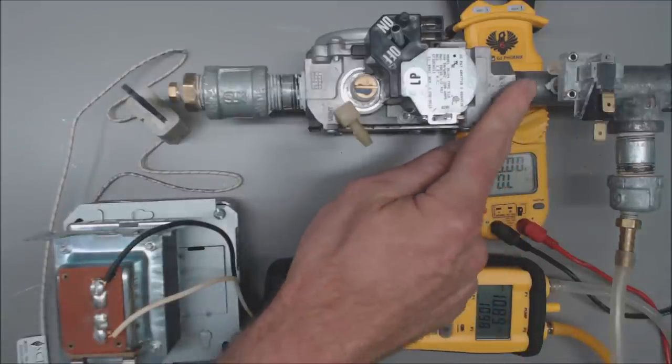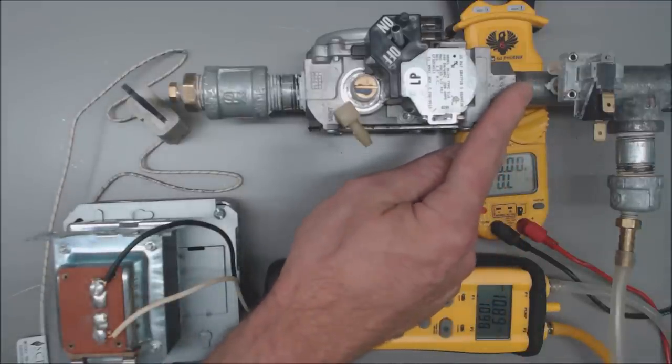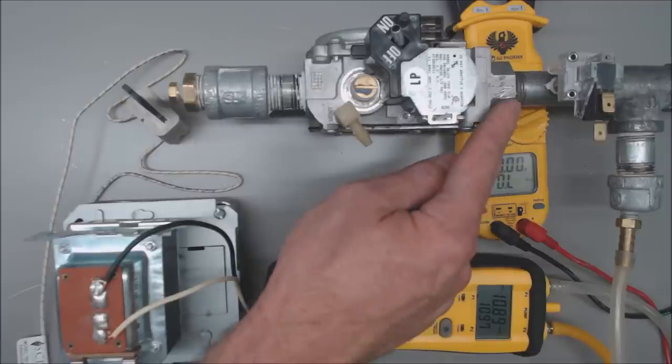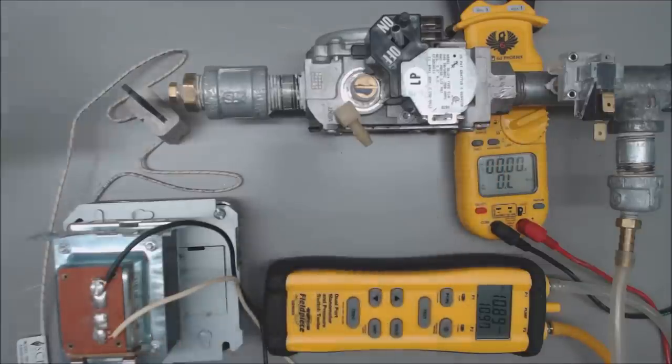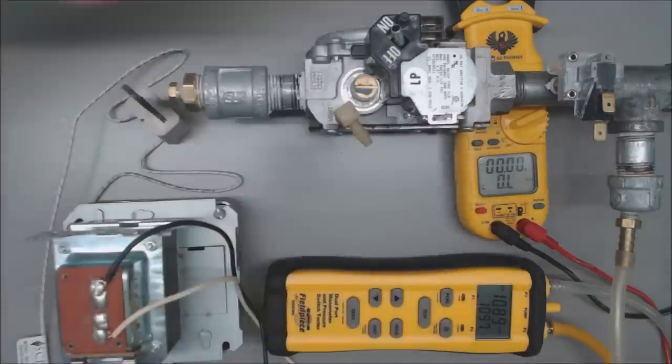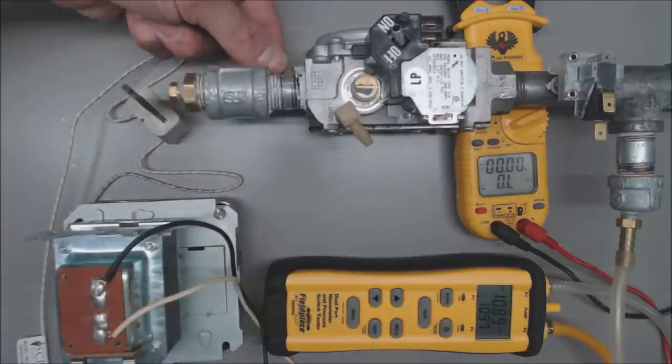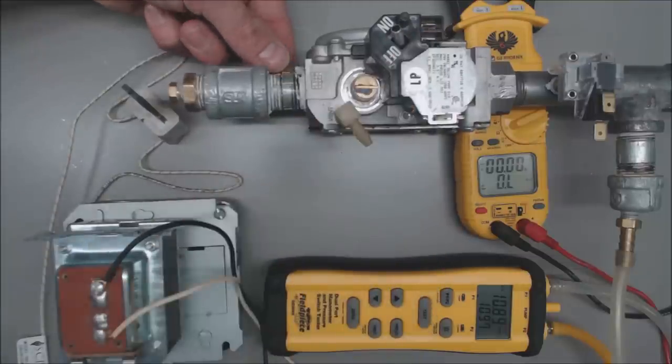So obviously if you don't have any gas pressure coming in that will be a problem right away, and then you just want to go ahead and find where the gas valve is turned off at. But in this instance we have gas pressure coming in, so we definitely want to check on this side, see what's going on when we apply 24 volts to this.